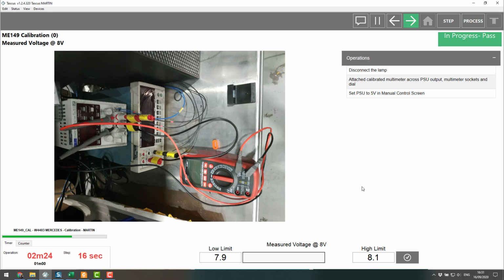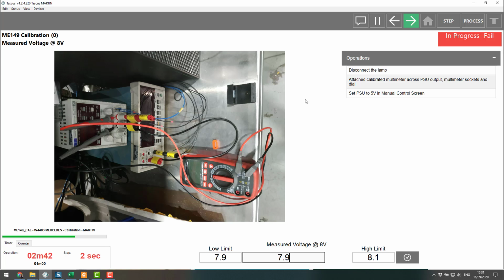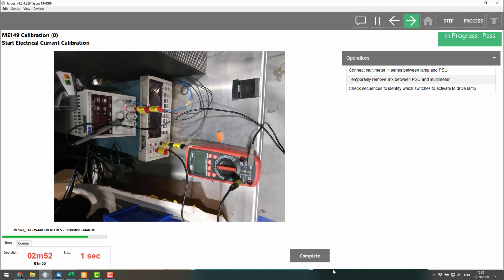So I can't do any adjustments in these. These are just a pass or fail. So for example, if I measured that was a 7.8, it would immediately give me a fail for the calibration. And I could say why that's the case. For now, I'm going to carry on. And it just guides me through each of the steps, asking me to take each of the measurements.